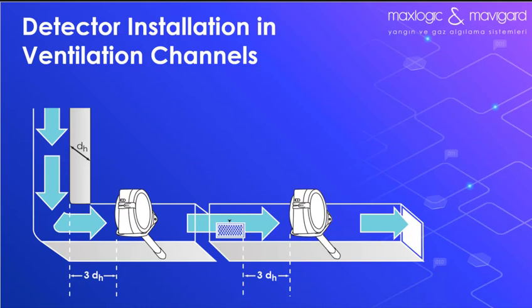6.5.1 General, detectors for air ducts. Air duct smoke detectors must comply with EN 54-27. To avoid the effects of air turbulence, smoke detectors or probes should be installed in a straight duct extension, away from a bend, corner, or at a distance of up to 3 times the hydraulic diameter of the duct.